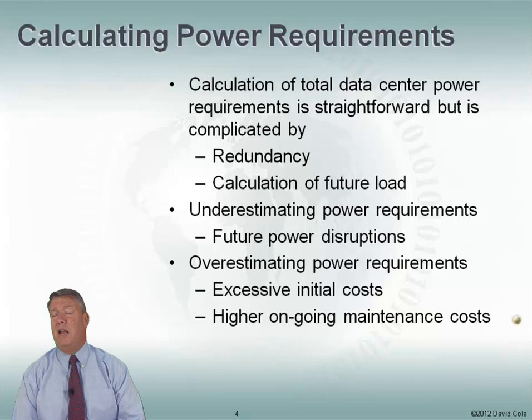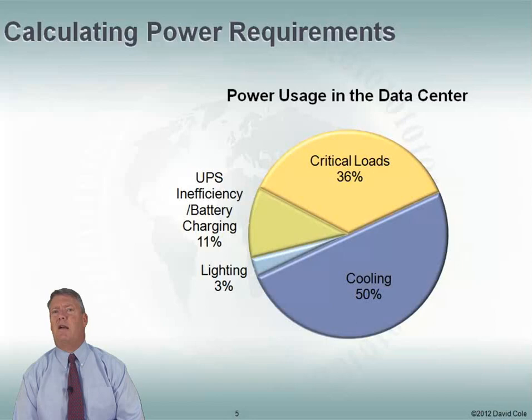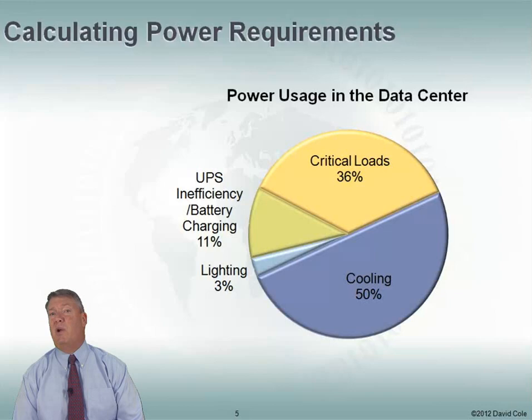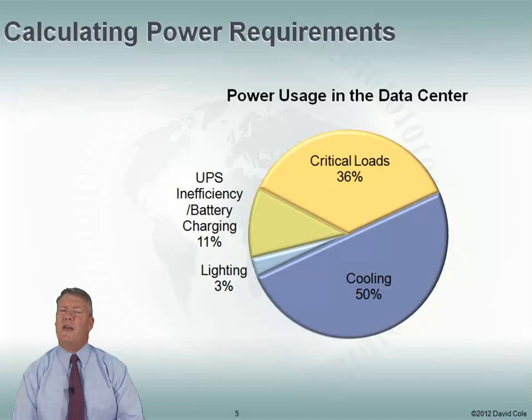Where is our power going in the data center? As much as half of it can go to cooling. We're going to talk quite a bit more about cooling and ways we can be more efficient, but cooling is often half the power in the data center. Then we have our critical loads, which can be a third or closer to a half. We also have UPS inefficiency when charging our UPS batteries, which can be quite a bit of our overall power usage. And then there's lighting.